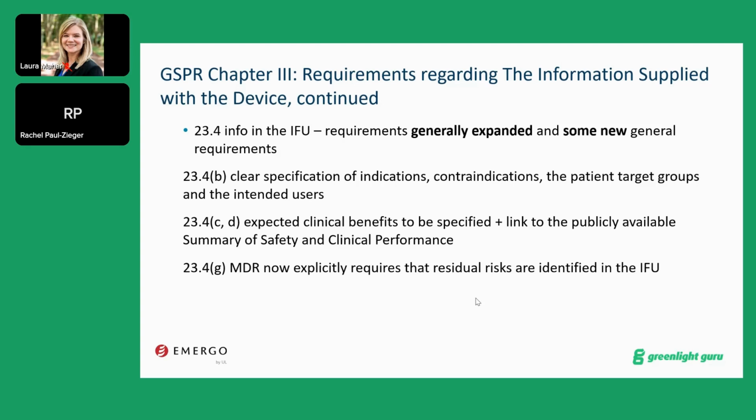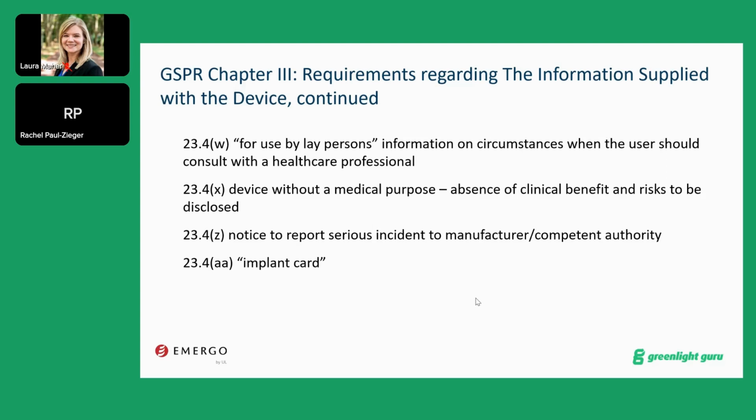And now the MDR explicitly requires that residual risks are identified in the IFU. You have a section for use by laypersons to include information on circumstances when the user should consult a healthcare professional. You have a requirement for devices without a medical purpose that you must clarify there is an absence of clinical benefit, and risk must be disclosed.